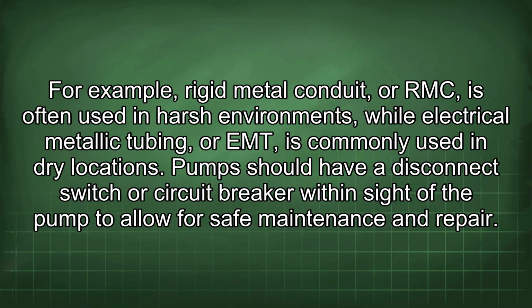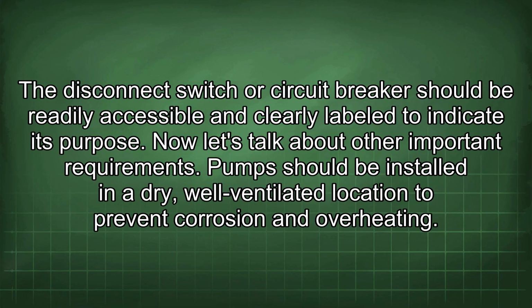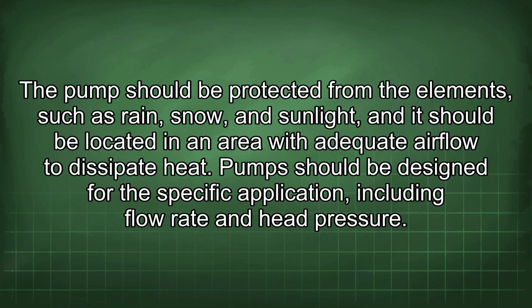Pumps should have a disconnect switch or circuit breaker within sight of the pump to allow for safe maintenance and repair. The disconnect switch or circuit breaker should be readily accessible and clearly labeled to indicate its purpose. Now let's talk about other important requirements. Pumps should be installed in a dry, well-ventilated location to prevent corrosion and overheating. The pump should be protected from the elements such as rain, snow, and sunlight, and it should be located in an area with adequate airflow to dissipate heat.